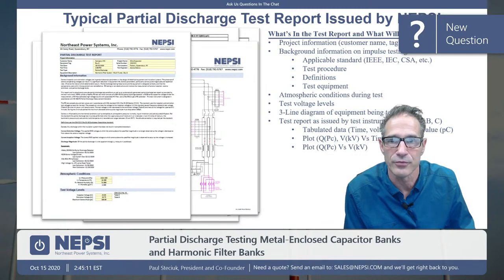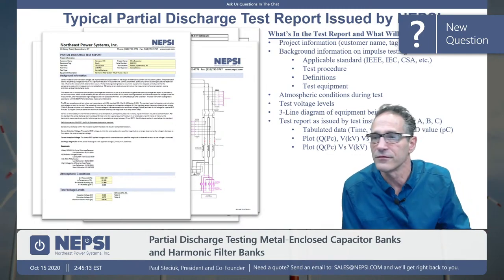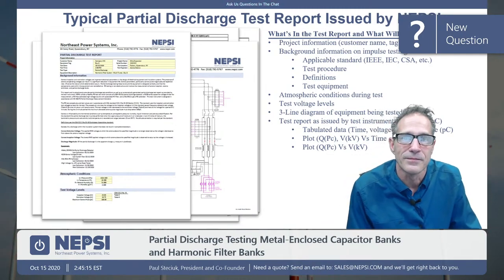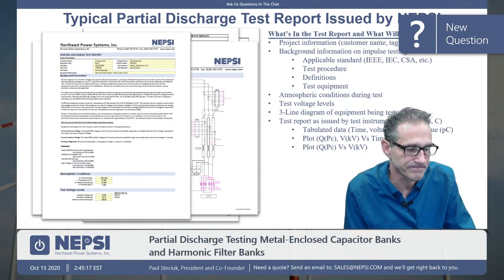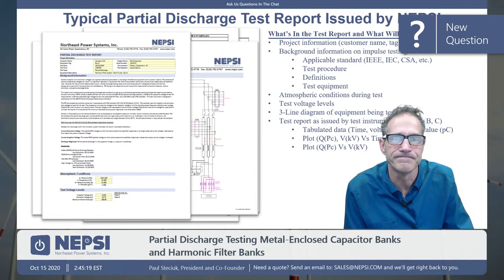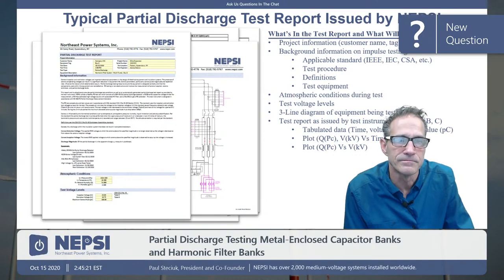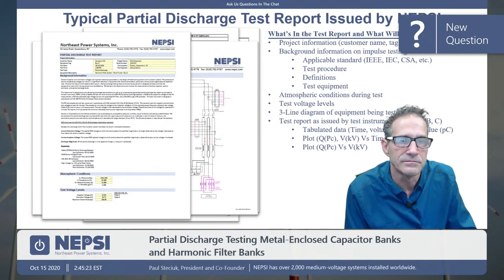So we're doing three tests per piece of equipment. And we got a question here. Yeah, another question from Garrett. He noticed that we tested at 50% of the BIL rating, and he's asking if the equipment is going to be protected by surge arrestors at that voltage rating.